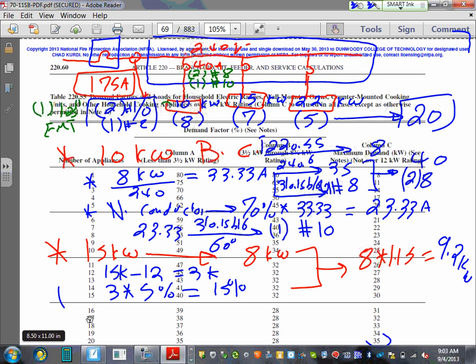Any comments, any questions, guys? I can't emphasize this enough. For branch circuit, you can apply the table. So now, the rest is history. Now you're going to take the 9.2 kW divided by 240. Can you guys do that for me, please? What's 9.2 divided by 240? 38.33. Take this one to 240.6. What would that give you? 40 amps.